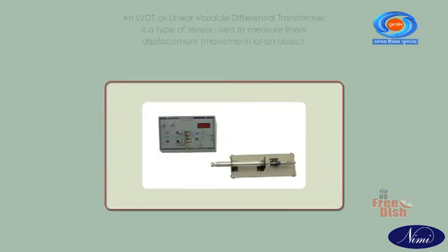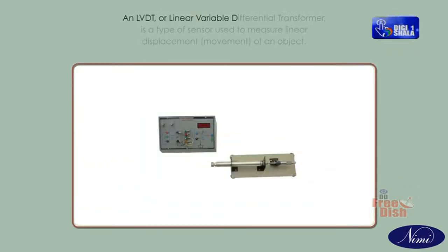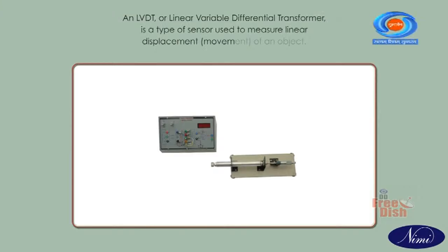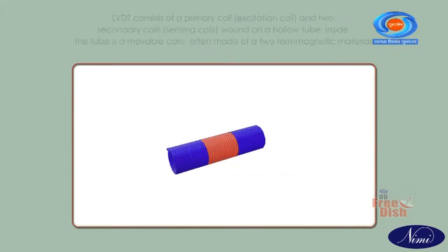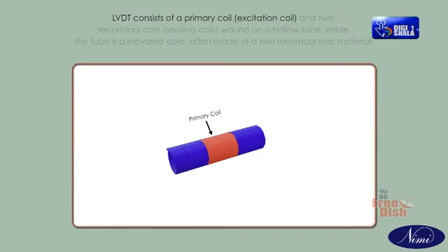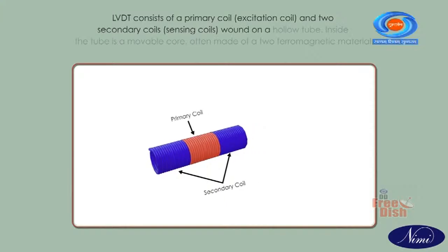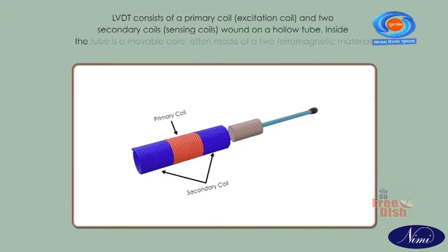Let us discuss LVDT. An LVDT, or linear variable differential transformer, is a type of sensor used to measure linear displacement movement of an object. LVDT consists of a primary coil, the excitation coil, and 2 secondary coils, the sensing coils, wound on a hollow tube. Inside the tube is a movable core, often made of a ferromagnetic material.